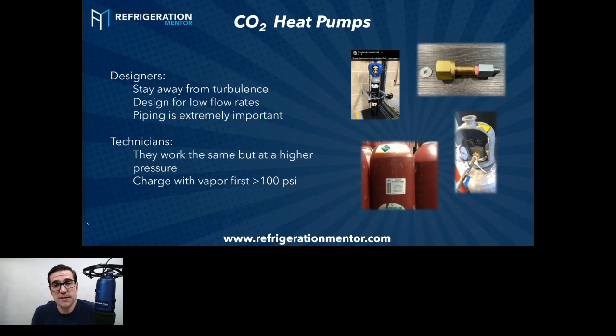When you go to charge this system now with CO2, you need the proper tools. You can't just use your regular gauges. You need hoses that can handle the pressure, because inside a CO2 cylinder at room temperature, you're over 800 psi. So if it's a hot day out there, you could have 1,000 psi in that tank. The hoses on the gauges you use today for your 410A, just say for an example, most of them are rated 800 psi maximum working pressure, 4,000 psi burst pressure. So now out of that cylinder, you see a few images here. We have 1,000 psi, so you want to use a different rated hose. Okay, you want to make sure that you're using the proper tools.